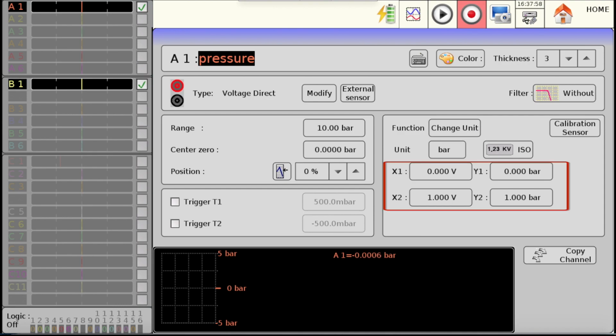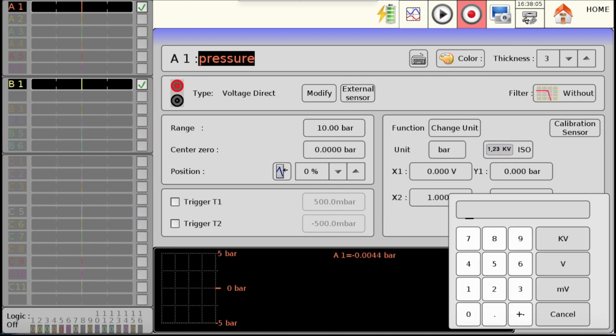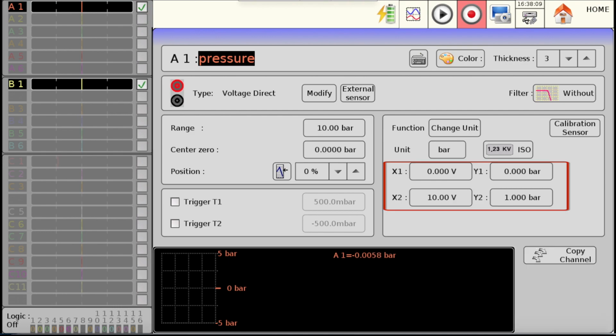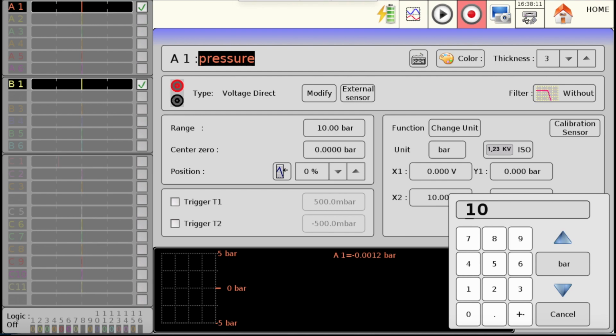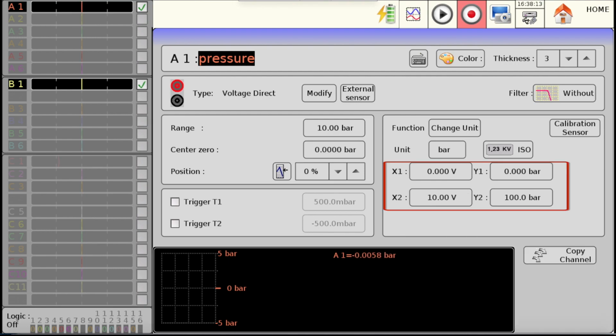For a measured value of 0 volt, we will have 0 bar, and for a measured value of 10 volt, we will have a measurement of 100 bars. Our change of unit is now set. You can see on the left of the screen that the range is now in bar.